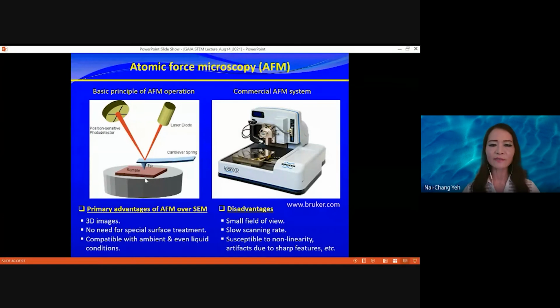I'll just show you the side view. You have a cantilever and a laser beam coming down, and you have a position-sensitive detector to detect where the light got deflected, and you can convert that information to the height. And then you also have the X and Y position. This can be done at room temperature, or you can cool it down, go to vacuum if you want. But this is a typical commercial atomic force microscope.